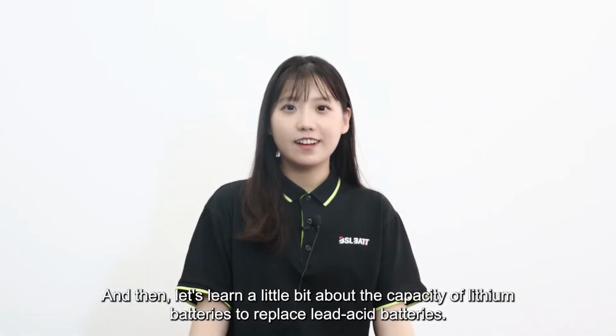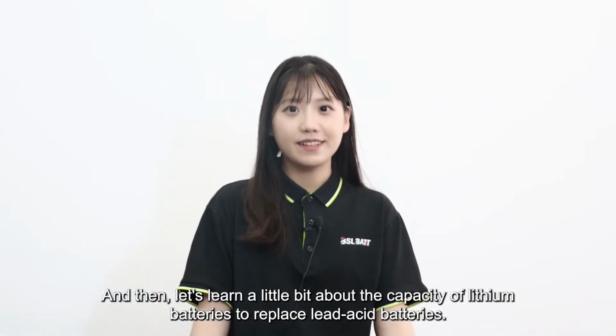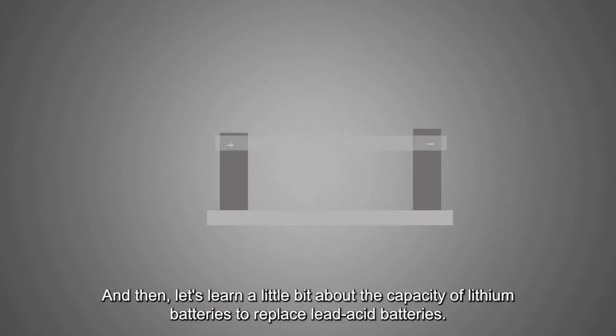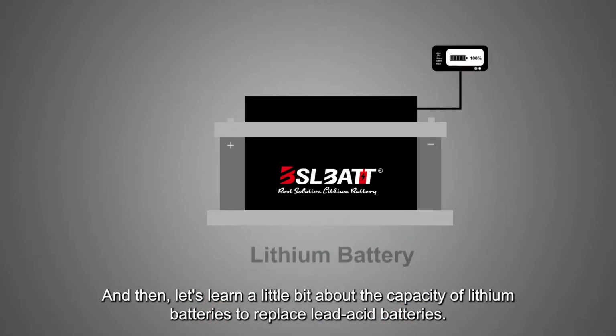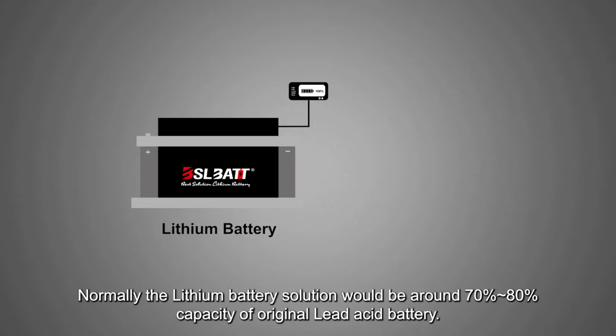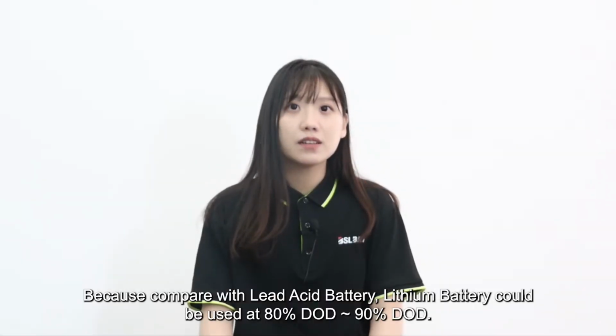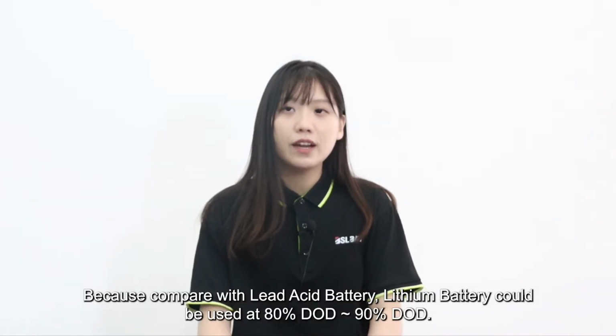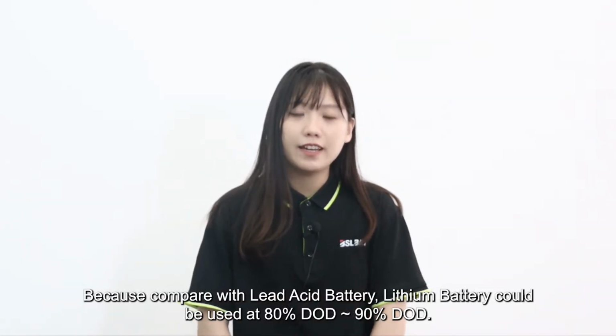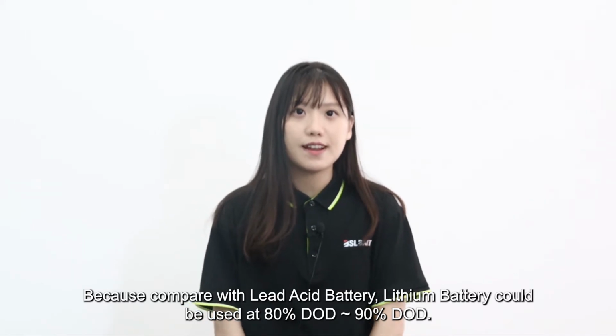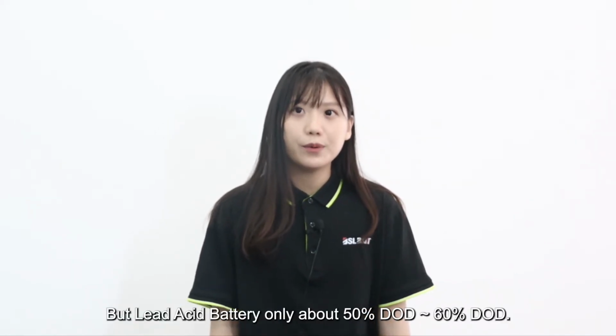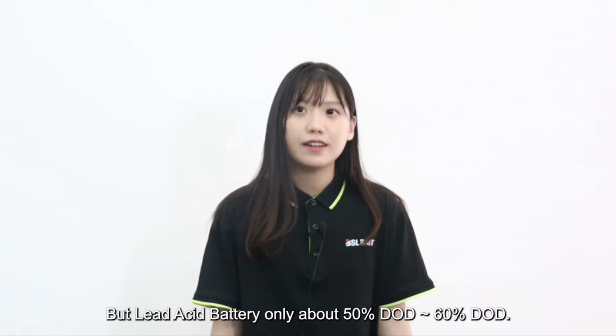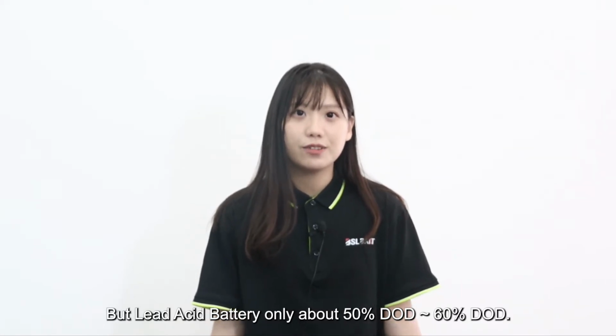Let's learn a little about the capacity of lithium batteries replacing lead-acid batteries. Normally, the lithium battery solution would be around 70% to 80% of the capacity of the original lead-acid battery, because compared with lead-acid batteries, lithium batteries can be used at 80% to 90% DOD, while lead-acid batteries are only about 50% to 60% DOD.